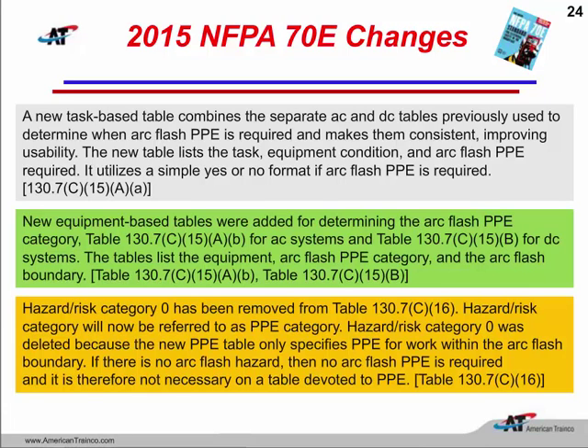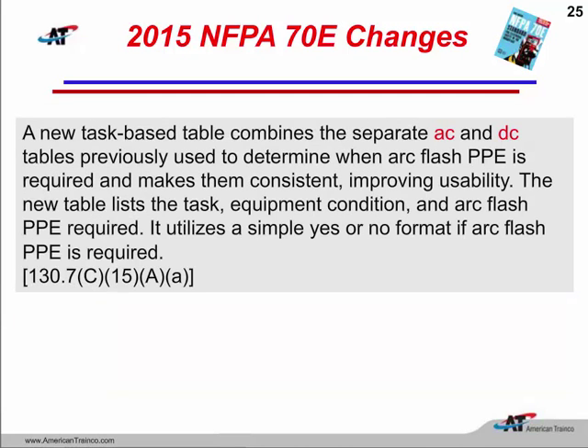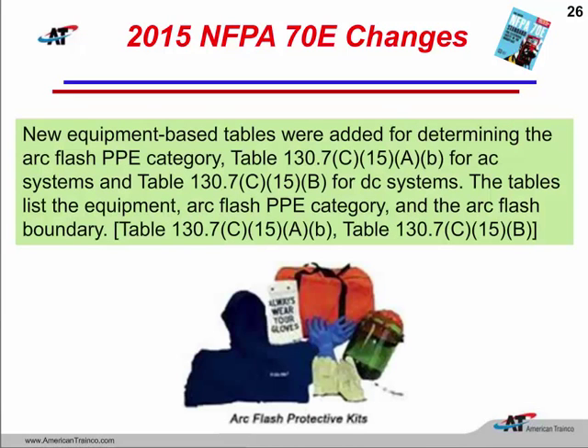So with that reasoning, why would we ever put an arc flash PPE Category 0 on a table when there really was no arc flash hazard there to begin with anyway? So they deleted hazard risk Category 0 from those tables. No longer will it be there at all. Also, we'll take a look at these tables, and we'll try to get a good handle on how we're going to answer these questions. We're going to give you a snapshot of these tables. We didn't include every single piece of equipment that NFPA 70E has in their table 130.7C15 because we just don't have enough room on these slides, but we're definitely going to give you a snapshot of these tables and give you an idea how to use these tables when you're out in the field.